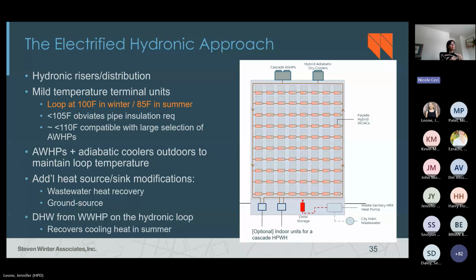So the basic approach that I'm talking about is one where we have a normal hydronic distribution running through the building. And that distribution is connected to what I'd call mild temperature terminal units. And I'll get into details on some of those terminal units in a couple more slides. But we're talking about distribution and terminal units that operate with a loop temperature of roughly 100 degrees Fahrenheit in the winter, 85 in the summer.